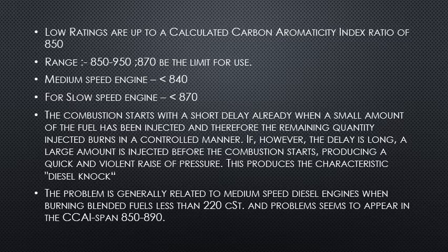The problem is generally related to medium speed engines when burning blended fuels of less than 200 cSt viscosity, and the problem seems to appear in the CCAI span of 850 to 890.